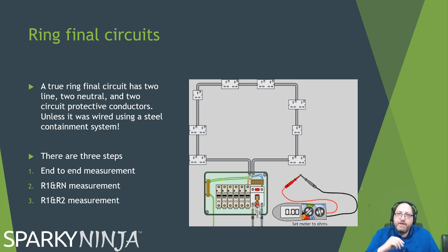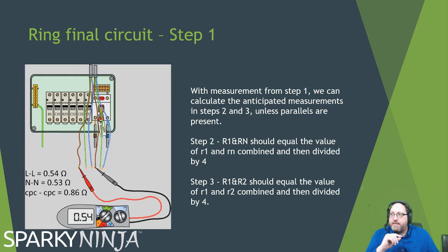So a true ring final circuit will have 2 lines, 2 neutrals and 2 CPCs. So this is like a spur-free ring final. There are 3 steps. Remember that, might be a question. There are 3 steps to the ring final circuit. The end-to-end measurement, the R1 plus Rn measurement, and the R1 plus R2 measurement. So the first step, the end-to-end measurement. This is to verify your ring is a ring.